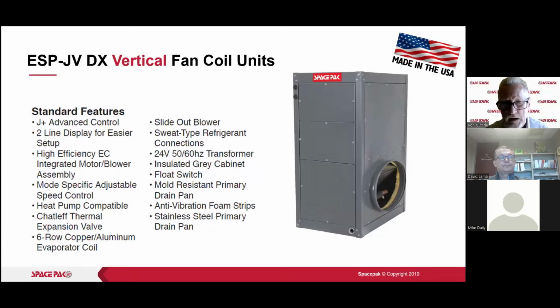All right, the vertical fan coil units, pretty much the same stuff. I don't really need to go through all those different features there, but I do want to point out something: this is not changeable in relation to the side of the unit that the return is on. If you look in there, you can see a little bit on this picture, that coil is slanted, so we need to come in on that side, that right side of the cabinet, to flow air over that coil. Now, what I have seen done out there in the field, and it has worked, is to put this up on a box if you can't return on this side, and run that box, a furnace box, for instance. But the only problem there is that you need to make sure that you have a smooth elbow transition up and into the return on the side of this unit.